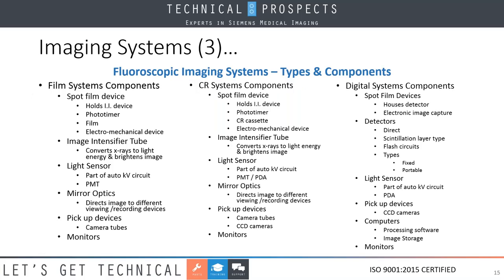When you look at the fluoroscopic imaging systems, this is strictly on the imaging side again. Again, I threw up all three of the different types of systems so that you can see some of the differences that have occurred. If you'll notice, they all have spot film devices. However, the spot film device has changed over time in terms of its overall function. The biggest thing back in the film and CR days is this was an electromechanical device, or maybe I should call it an electromechanical nightmare, especially when it came to the calibration. However, the new ones today, we've removed all that because we use electronic image capture as opposed to having to shuffle a film in and out.